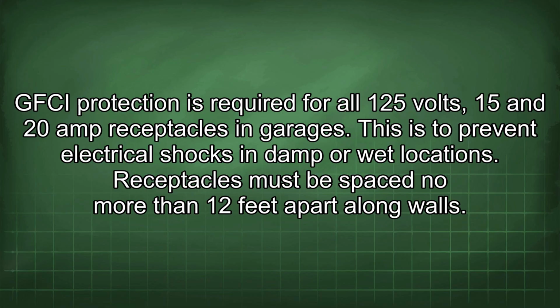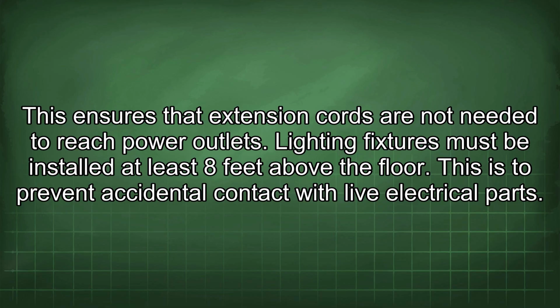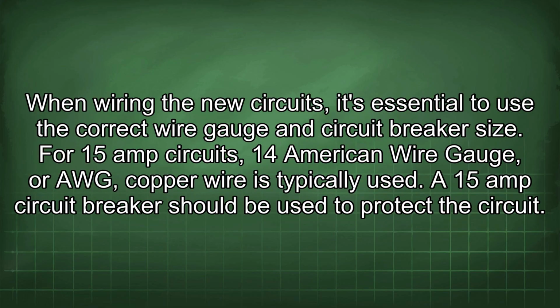Receptacles must be spaced no more than 12 feet apart along walls. This ensures that extension cords are not needed to reach power outlets. Lighting fixtures must be installed at least 8 feet above the floor. This is to prevent accidental contact with live electrical parts. When wiring the new circuits, it's essential to use the correct wire gauge and circuit breaker size. For 15-amp circuits, 14 American wire gauge, or AWG, copper wire is typically used. A 15-amp circuit breaker should be used to protect the circuit.